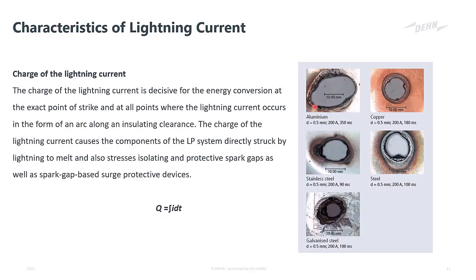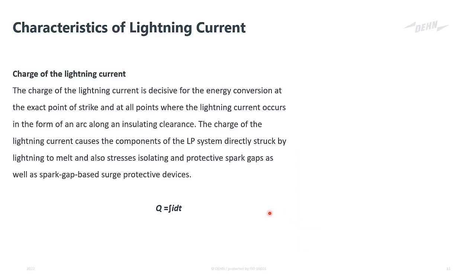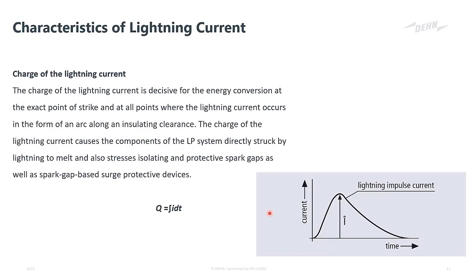Now here you can see some examples of different materials, the amounts of charge onto those materials, and the puncturing of the material. So this charge is responsible for melting objects at the point where it's terminated. If we look at this impulse of lightning current again, the charge is the integral of this impulse, or the area under the curve. So it's the integral of the current over time, or the area under the impulse curve. That would be the charge contained within that lightning impulse.